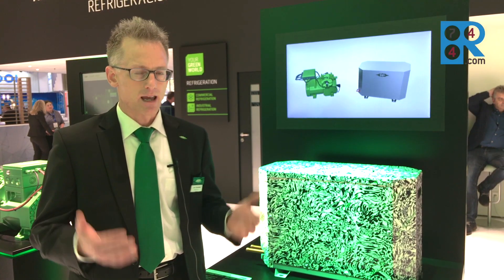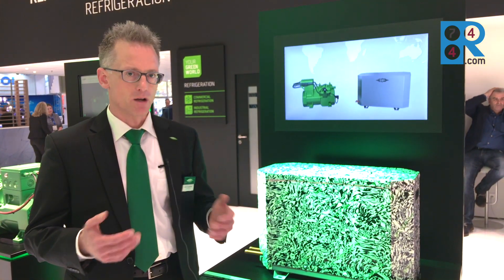This Expander offers, under ambient temperatures of 32 degrees C, a plus in efficiency and cooling capacity of more than 20 percent. The principle relies on the fact that we have a mechanical subcooling without additional power input required.